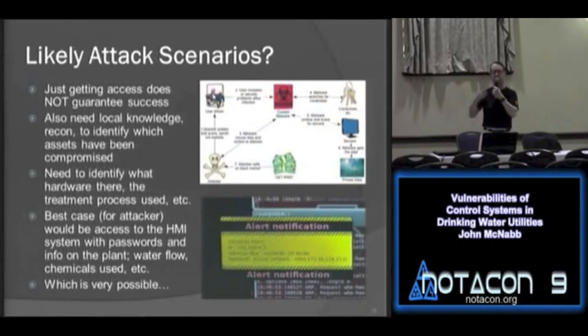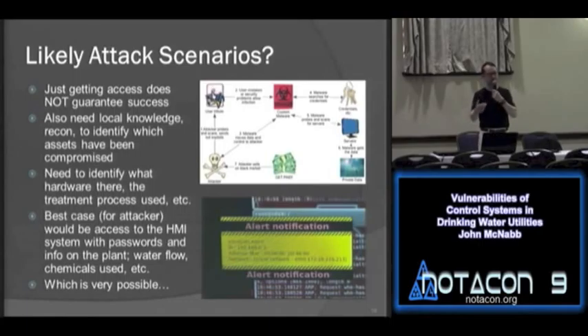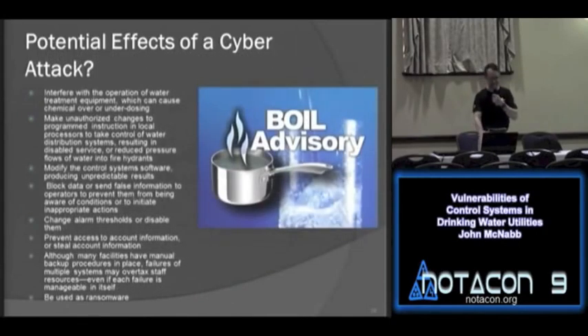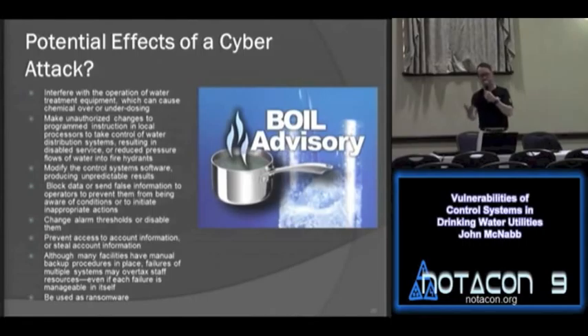Likely attack scenarios — the bad guys can't get in just because a system is on the internet or accessible via mobile or remote; they have to know something about the system. But once you get into the human machine interface, it's really all point and click — it's not that hard. Potential effects of a cyber attack, from the government report 'Roadmap to Control System Security in the Water Sector,' include: shut down the water, send too much water, change the chemical mix, change alarm thresholds, and so on.